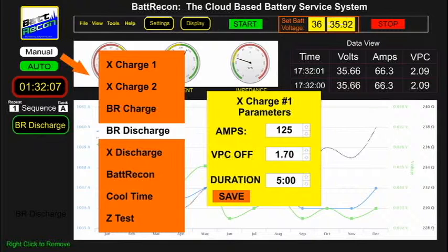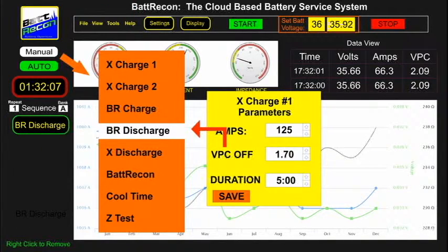Now that we've covered all of the available device mode selections, let's go back to the original manual mode example: to discharge a battery one time using the BattRecon discharge device at 125 amps until the calculated volts per cell, or VPC, reaches 1.7. We left-click on the manual tab and the drop-down window appears listing all available devices. We left-click on the BR discharge device, then a parameters window appears.